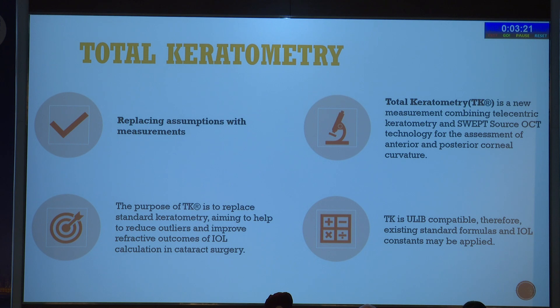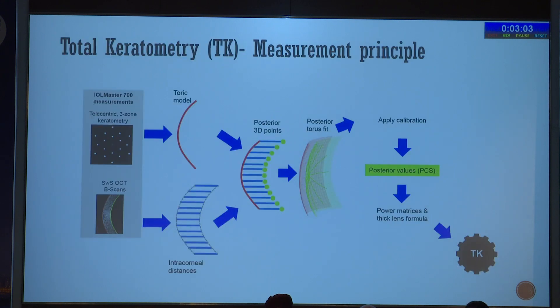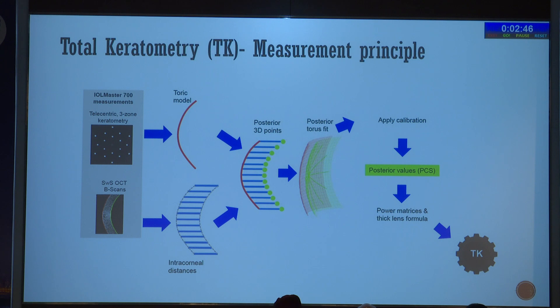Total keratometry was a new measurement combining telecentric keratometry and swept-source OCT technology for assessment of anterior and posterior curvature of the cornea. It was ULIB compatible and therefore could be used with existing standard formulas, and IOL constants could be applied. Using the same basic model of 3-zone telecentric measurement with swept-source OCT, this TORIC model predicts the posterior corneal curvature much better, and thus a total corneal keratometry is measured using the anterior and posterior values.